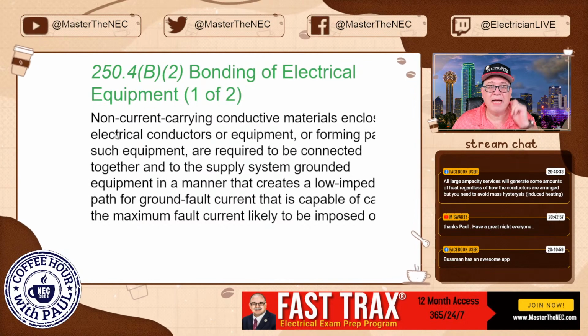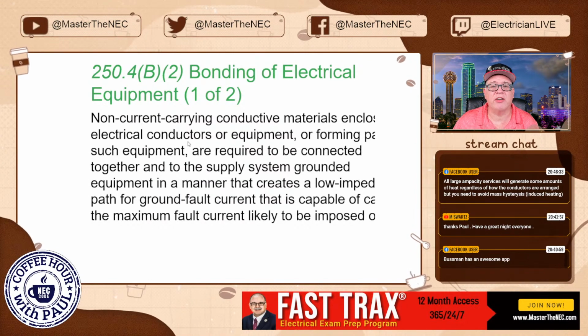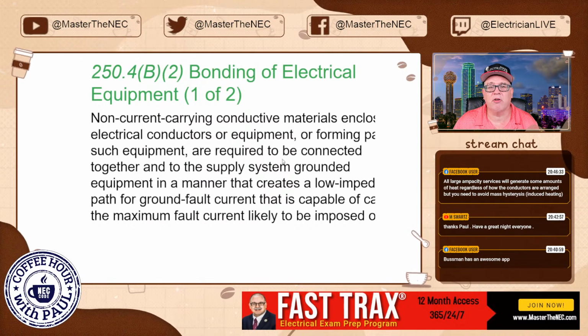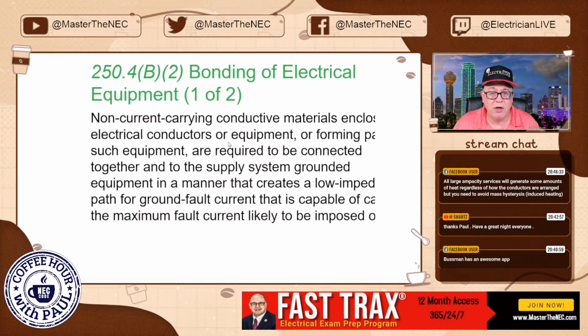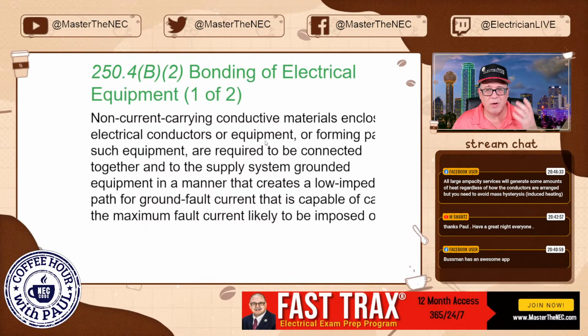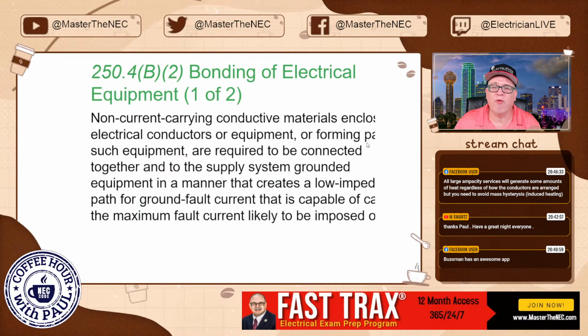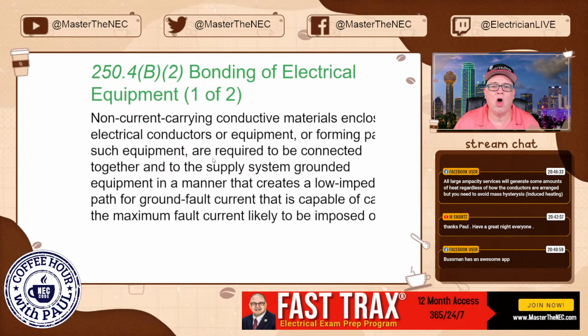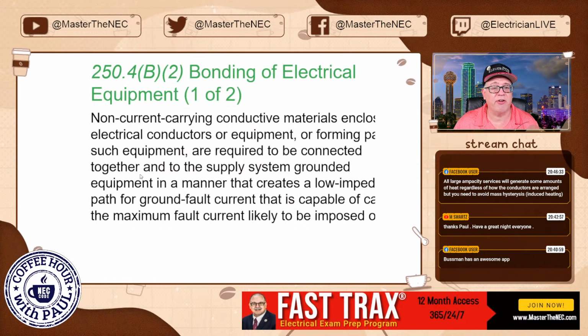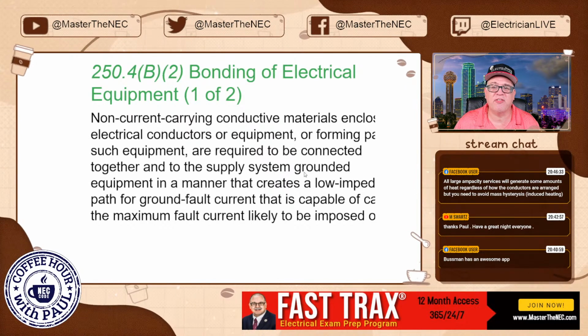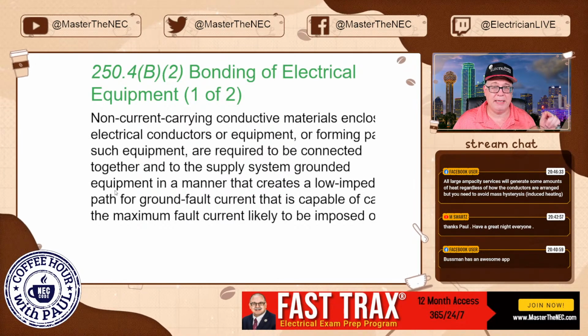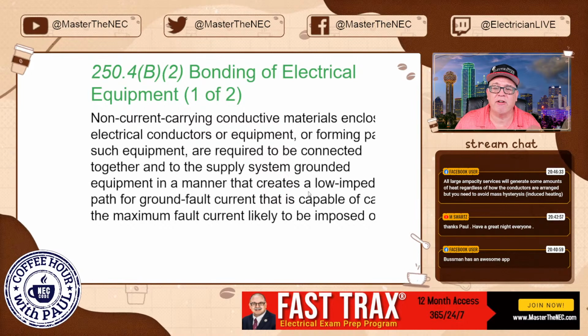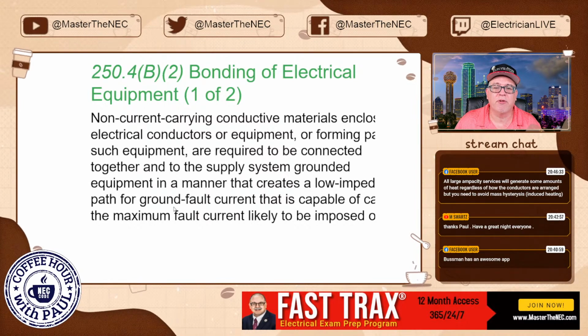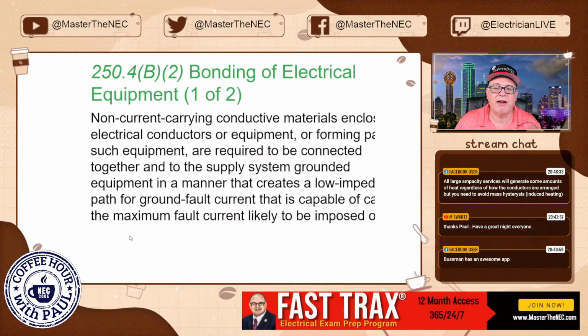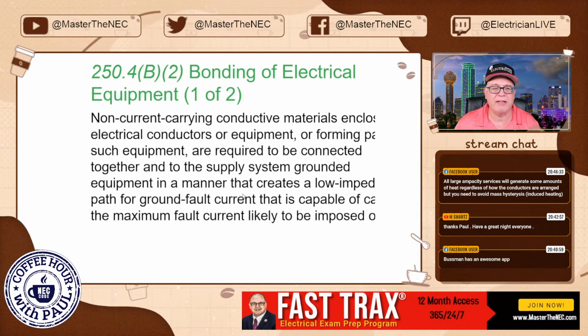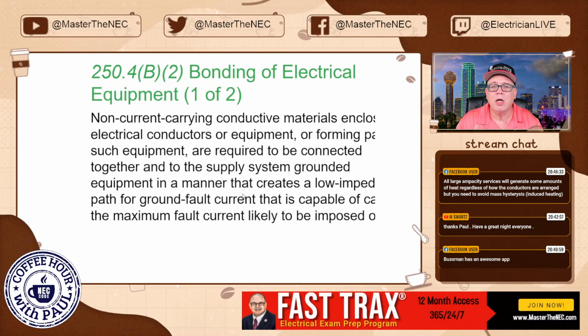All right, next, 250.4(B)(2), non-current carrying materials enclosing electrical conductors or equipment, raceways and whatnot, or forming part of such equipment are required to be connected together and to the supply system grounded equipment in a manner that creates a low impedance path for ground fault current that is capable of carrying the maximum fault current likely to be imposed on it. So, interesting thing.